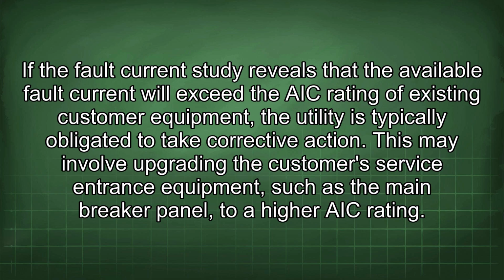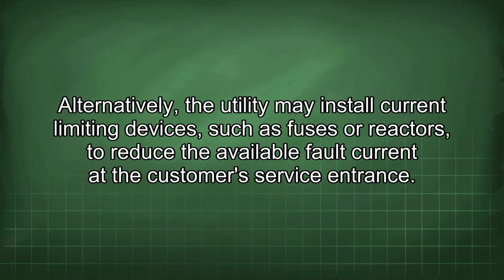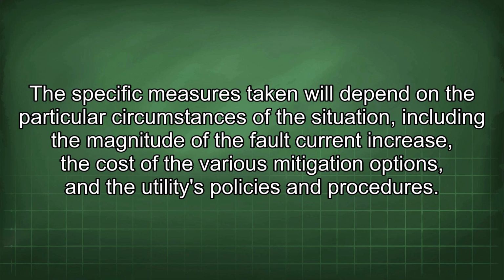This may involve upgrading the customer's service entrance equipment, such as the main breaker panel, to a higher AIC rating. Alternatively, the utility may install current limiting devices, such as fuses or reactors, to reduce the available fault current at the customer's service entrance. The specific measures taken will depend on the particular circumstances of the situation, including the magnitude of the fault current increase, the cost of the various mitigation options, and the utility's policies and procedures.